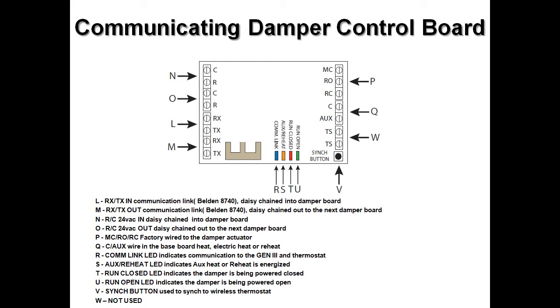The communicating damper board simplifies the daisy chain wiring with the CR terminals for power in and out, along with the communications loop terminals in and out labeled RX and TX. MC, RO, and RC, motor common, run open, and run closed terminals are factory wired from the Belimo actuator to the damper board, where AUX and C terminals are also available to support supplemental heat options like baseboard, duct heaters, or a coil in a box.